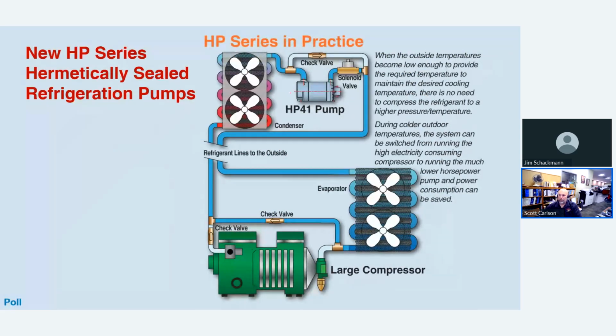The way the economizer packages work is when you have a refrigeration system that's cooling something, it's using a large compressor. That compressor can be anywhere between 10 horsepower up to 30 horsepower, and it has to run 24 hours a day, 7 days a week in order to keep the system cool. And with this economizer package, it can be installed in such a way that it is put on the roof with a heat exchanger on the roof of the building. And on days when it's cool outside or at nighttime when it's cooler, as long as the temperature is lower than what they're trying to cool on the inside, they can turn off this compressor and bypass it and use the outside air for doing that.